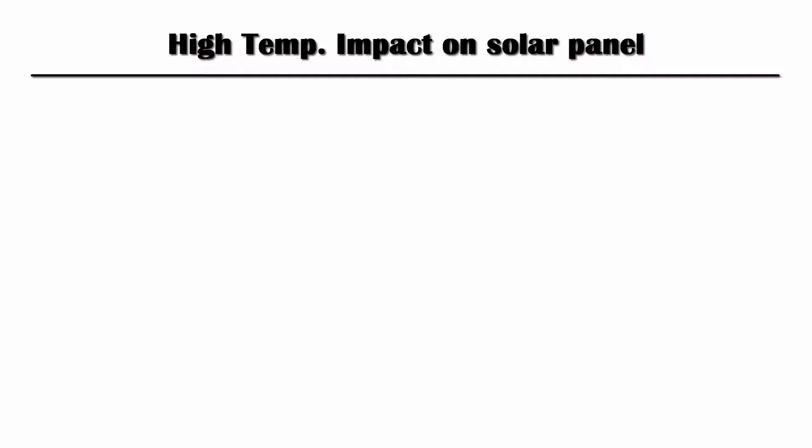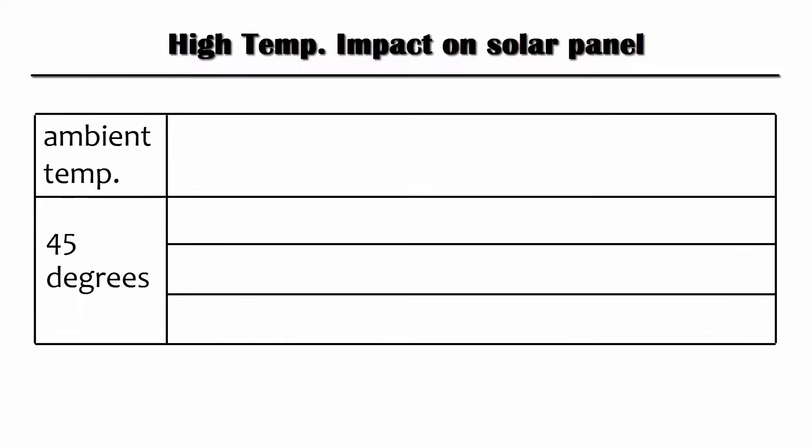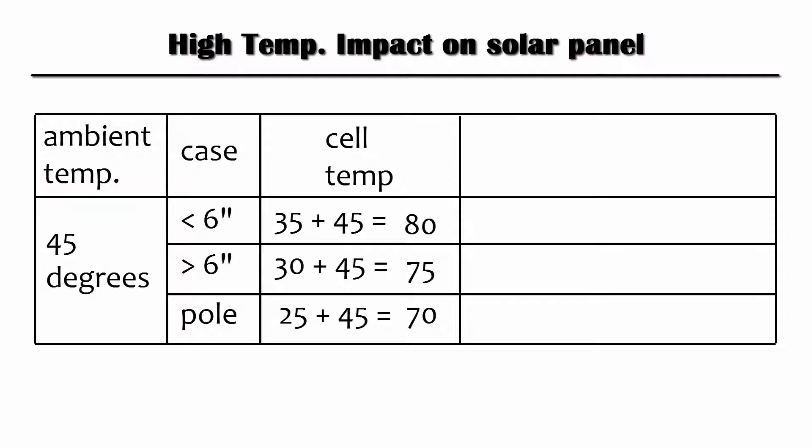If the highest temperature in your location is 45 degrees Celsius, the cell temperature will be 80 degrees, 75 degrees, or 70 degrees according to the type of mounting and the distance between the back of the module and the mounting surface.